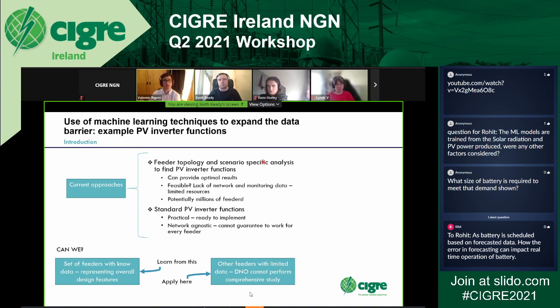That's very practical for utilities because it's going to be better than not using anything or just coming out with parameters with no logic. But the problem is that they think that solution is going to work for any network, regardless of what the characteristics of the network are. The problem with the LV system is that you can have a transformer and a feeder that has 20 customers, and next to it, a feeder that has 150 customers. And they're totally different in terms of topology. So you cannot expect the same standard function to work in both cases.